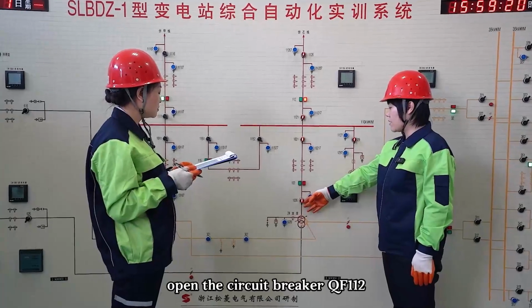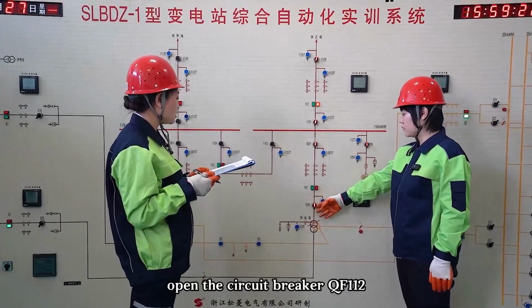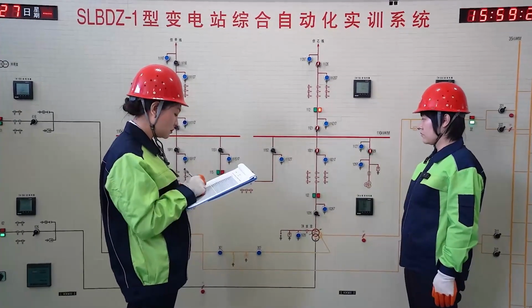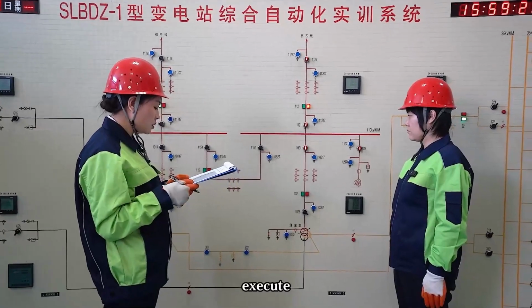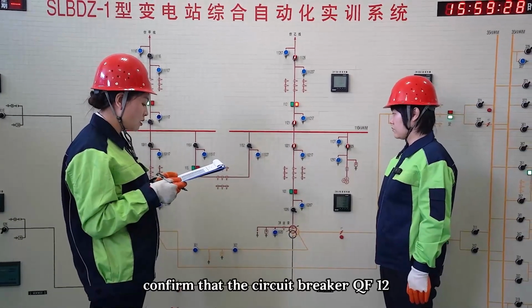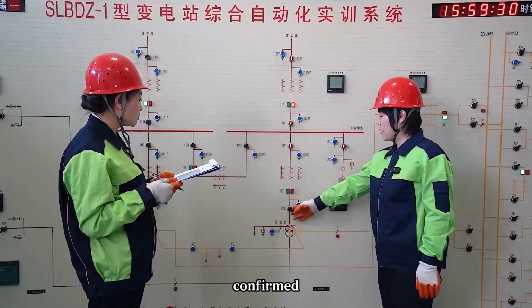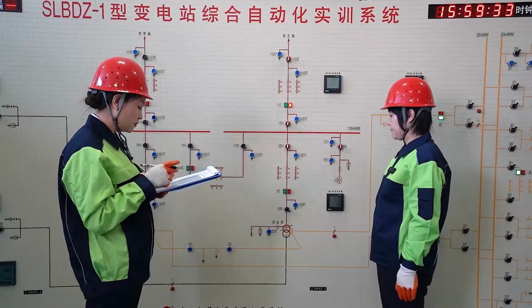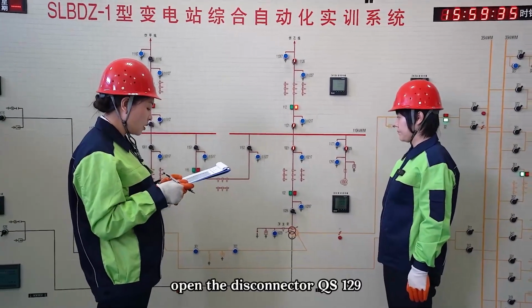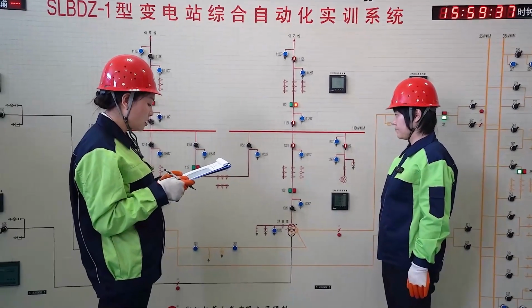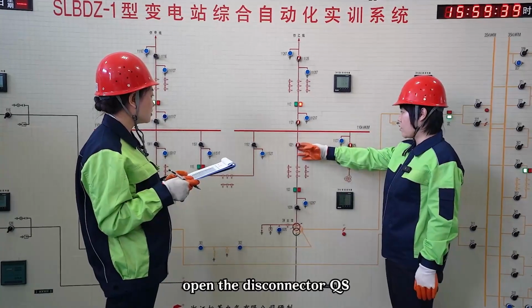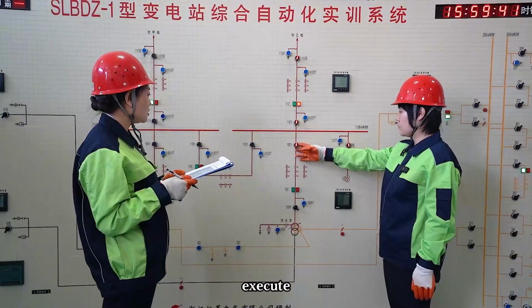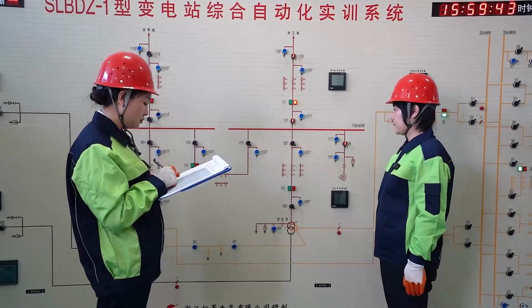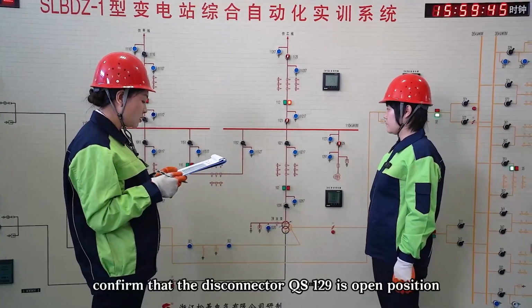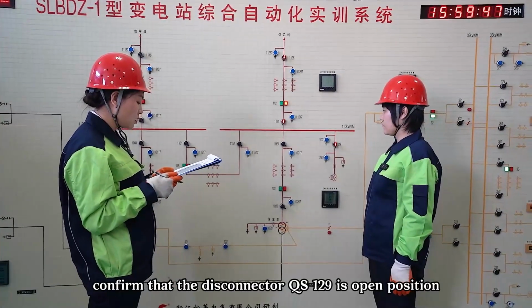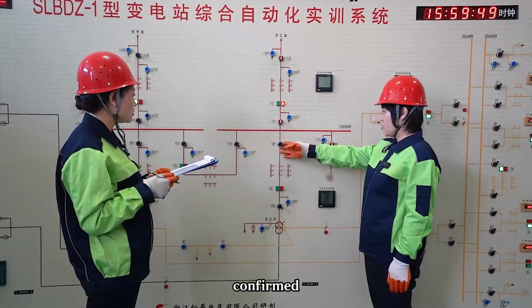Confirmed. Open the circuit breaker QF112. Execute. Confirm that the circuit breaker QF112 is in the open position. Confirmed. Open the disconnector QS129. Execute. Confirm that the disconnector QS129 is in the open position. Confirmed.